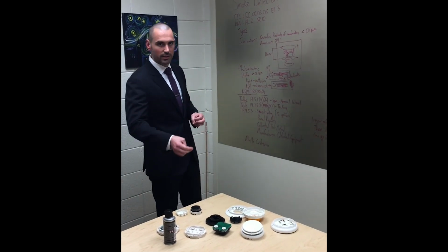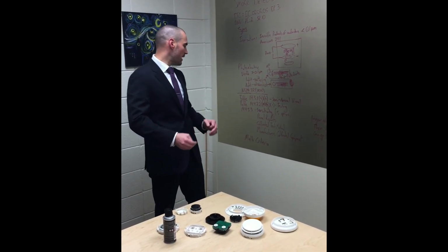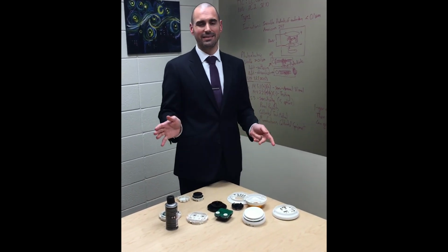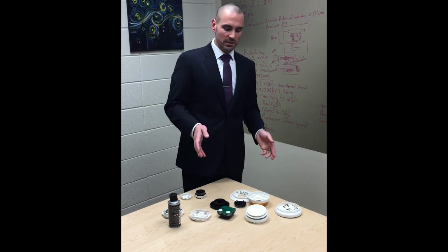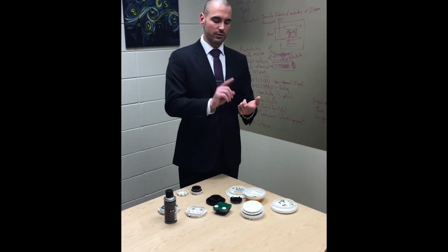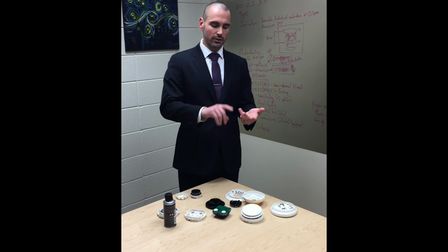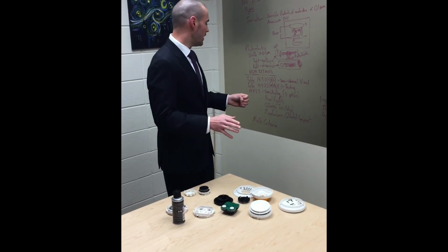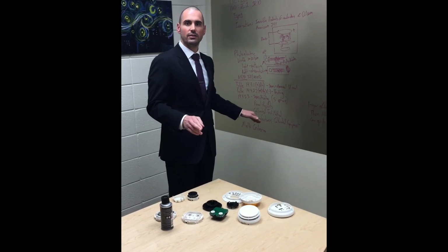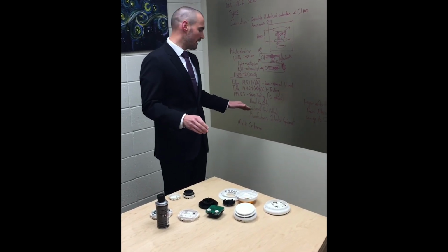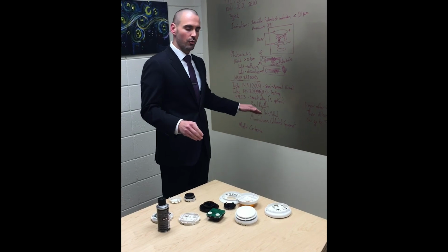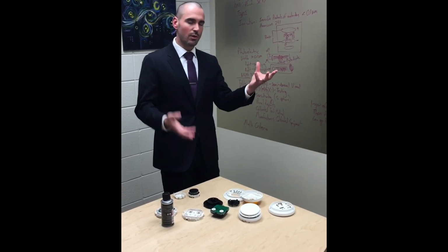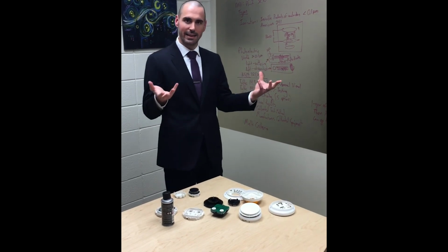One last thing to mention before we call this one a wrap is multi-criteria detectors. We're really not going to do a series on these, but some detectors have multiple functions. You can do smoke, rate-of-rise heat detector, and fixed temperature heat detectors. All of that can go together, but multi-criteria detectors have to do individual tests. You have to test every function of a multi-criteria detector. So if it's smoke and heat, you have to test the smoke and the heat.